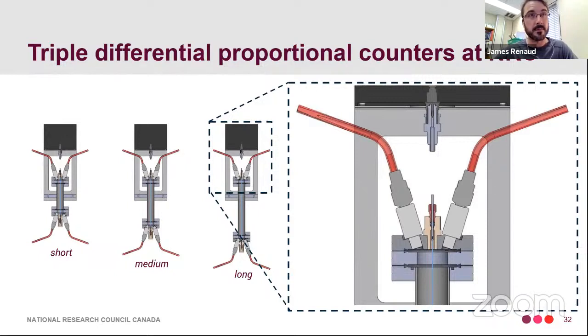So as a recap, the proportional counters are filled with a mixture of radioactive gas and P10. Following radioactive decay by beta emission, the particles emitted ionize the P10, and the electrical charges created are collected by means of a high voltage across the wire in the wall. The signal given by the number of charges collected will be proportional to the absorbed radiation energy. And the number of detected decays per second is proportional to the activity of the radioactive gas present in the counters. In the design you'll see here, each counter is mounted vertically, and this is to avoid sagging of the wire.